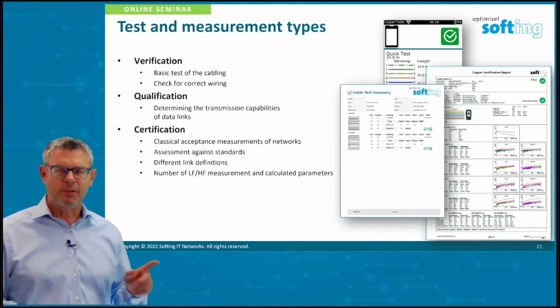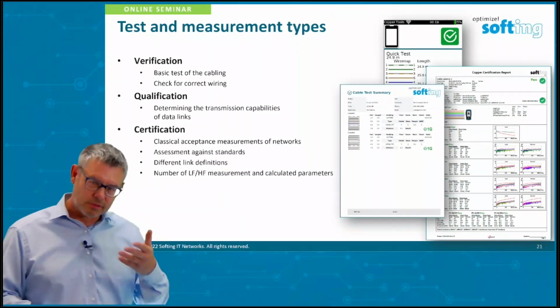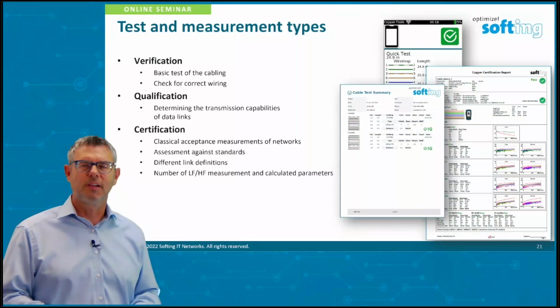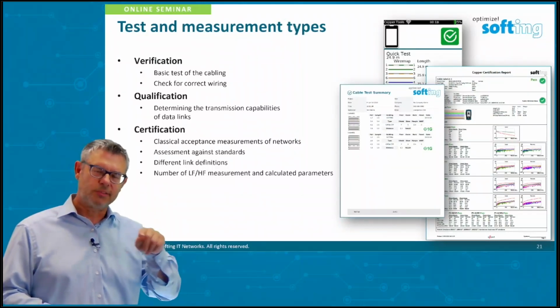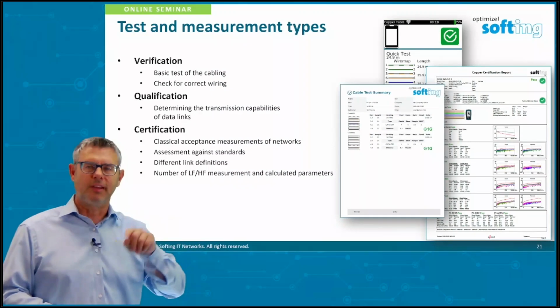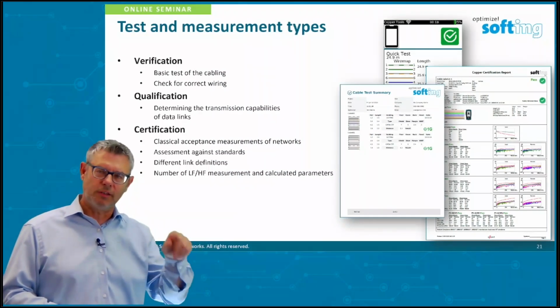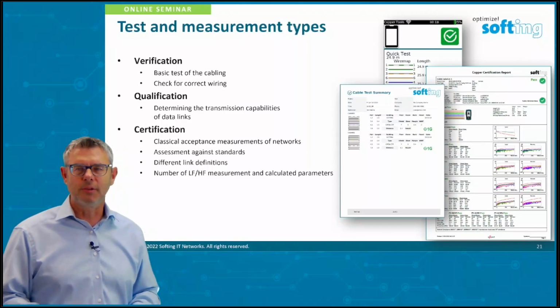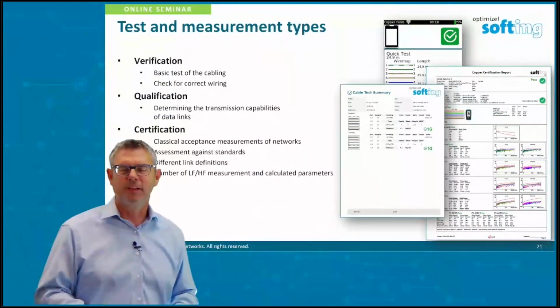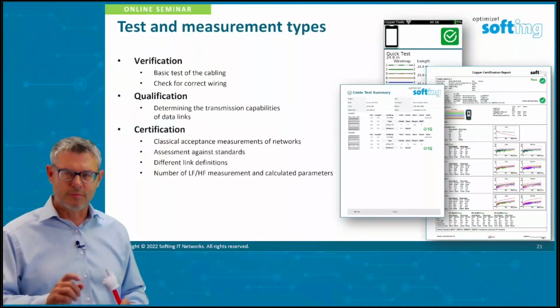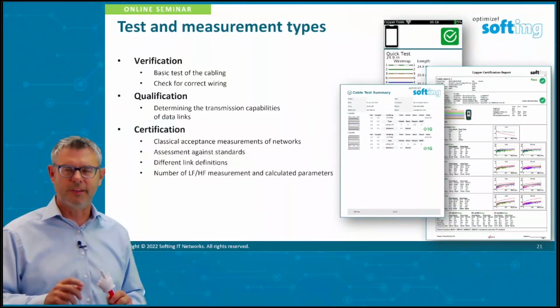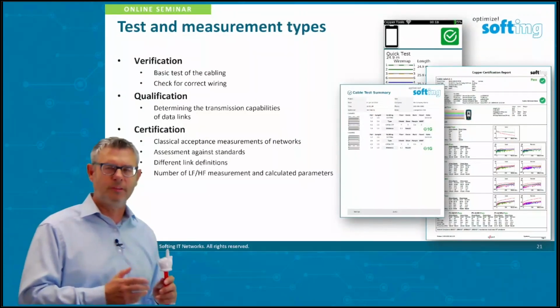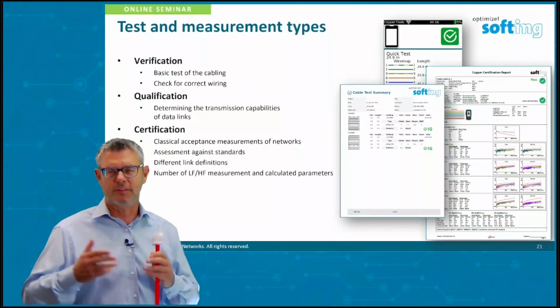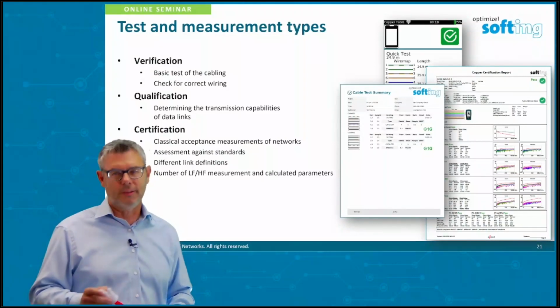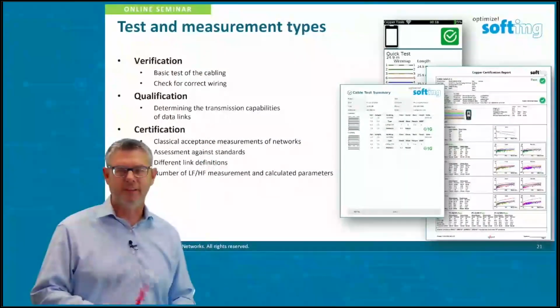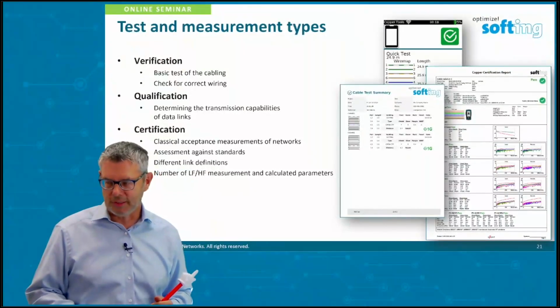Because in the Ethernet parameters, where Ethernet is defined as a transmission protocol, it's also referenced how many faults are allowed in a transmission process to say that the transmission media is working or not. That's the basis behind it. So it's doing a kind of bit error rate testing, as we see later on, to analyze the quality of the transmission line. And you can use this test as documentation that this application will work on this installed basis. The advantage is that the instrument is cost-wise somewhere in the middle between verification and certification.